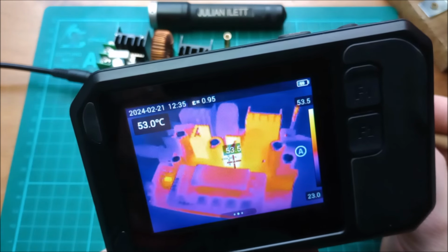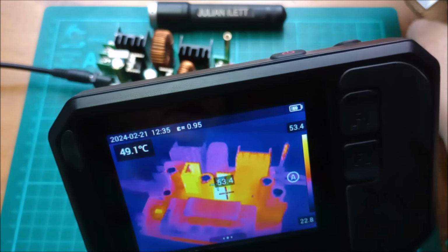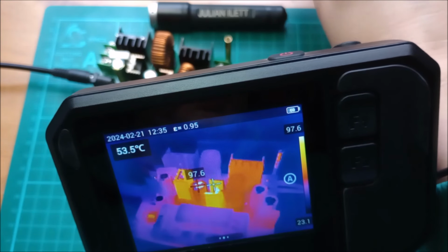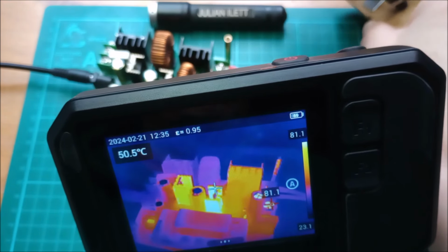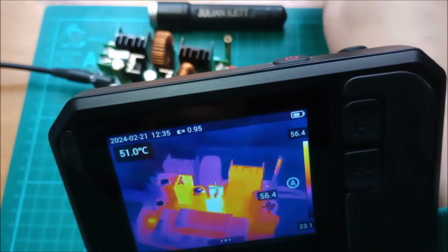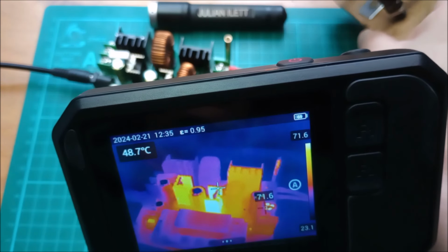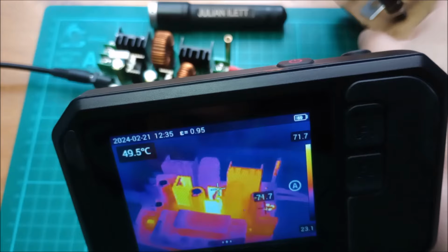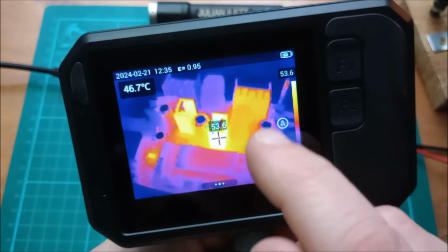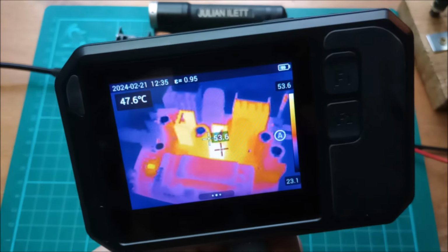And with any thermal imaging, you've just got to watch for certain things, like the tops of these capacitors look quite cool, but actually that's a reflection rather than an emission. And if I move the light bulb so that it reflects into the tops of those capacitors, yes, you can see that they are reflecting the window actually in my office. And if I move the light bulb onto the top of them, you can see the little four quadrant vents on the tops of those. So you do have to use the usual analysis of things that may look cool, but they're actually reflecting rather than emitting.